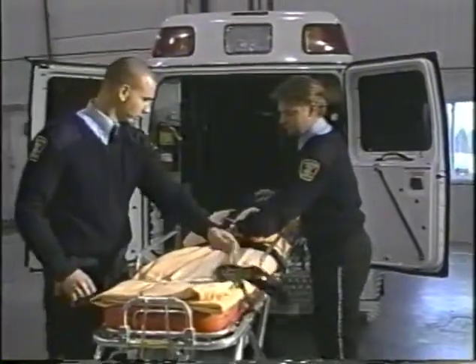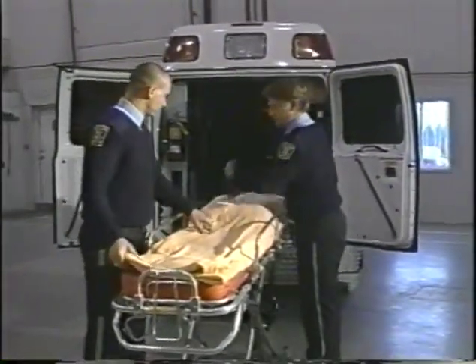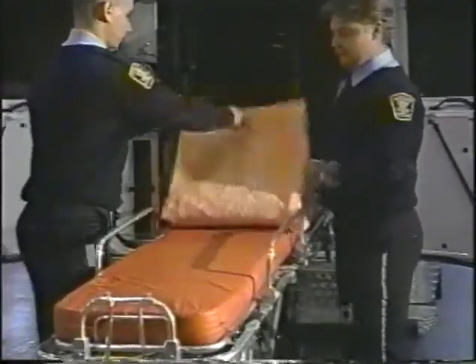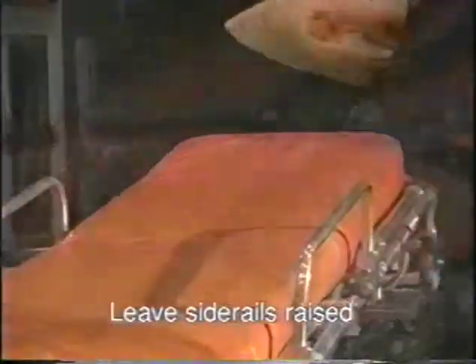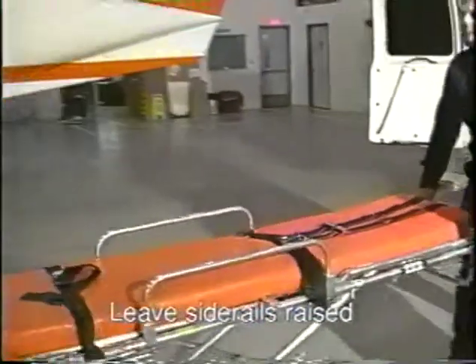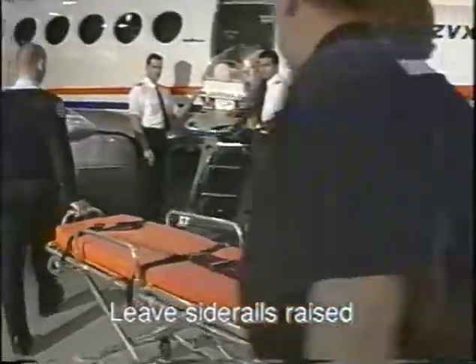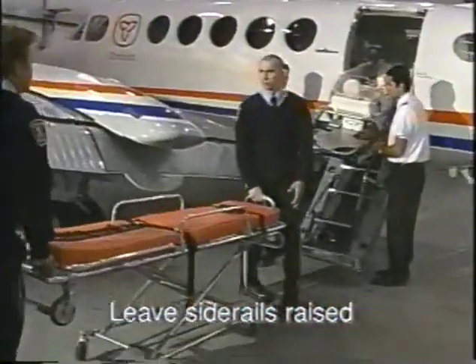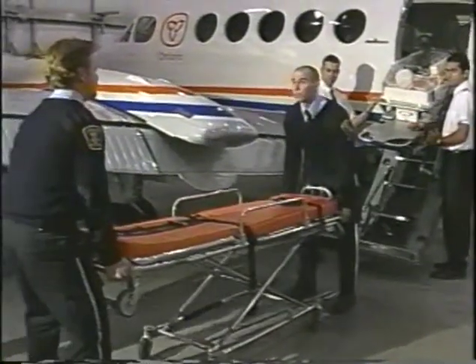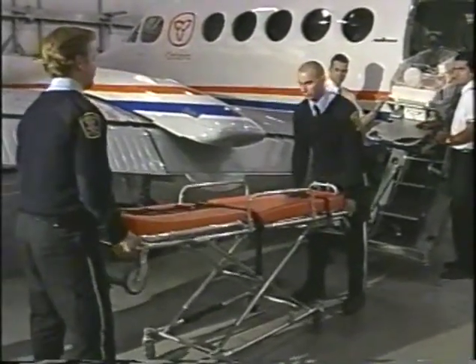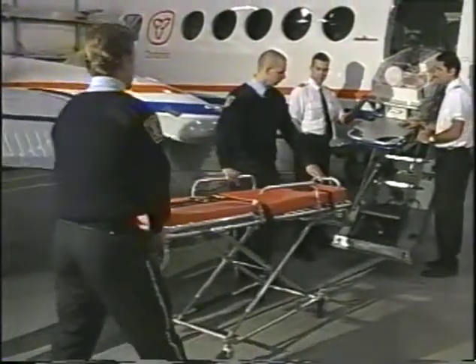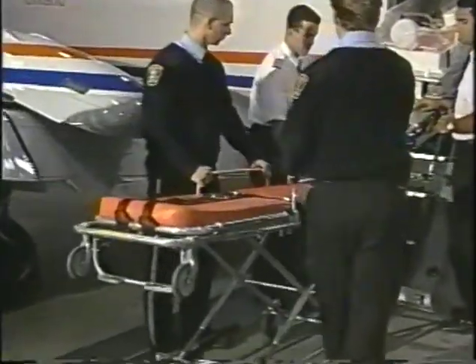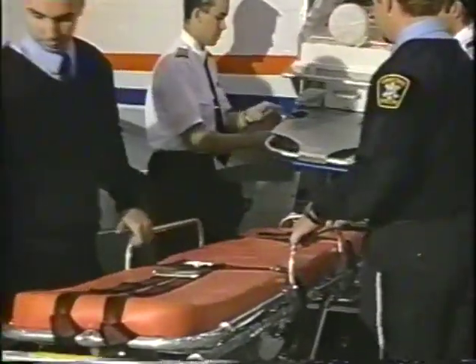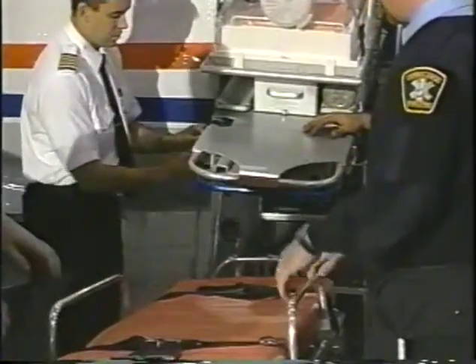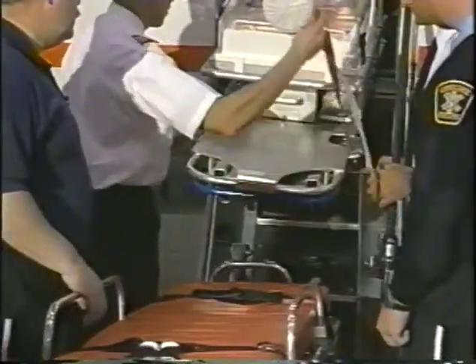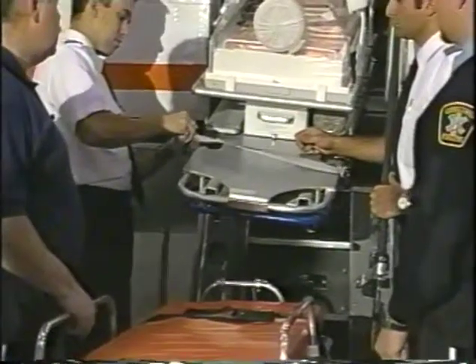The land EMA paramedics prepare the 35A stretcher in the usual manner. Put both side rails of the 35A stretcher up so they act as a reference guide for placing the adapter deck evenly on the mattress. Lower the 35A to a height just below that of the loading ramp. They will position themselves and the 35A at the end of the loading ramp so that the 35A stretcher is as close as possible to the loading ramp in order to reduce the distance required to carry the adapter deck.